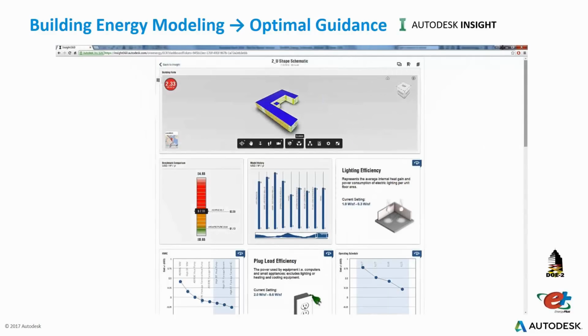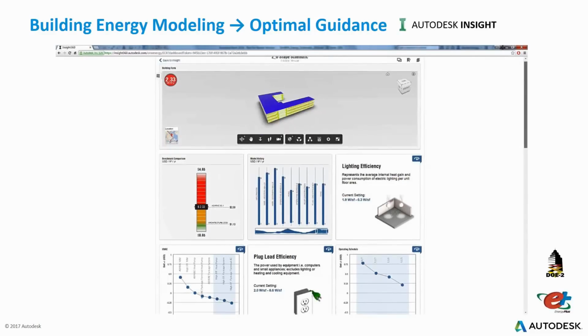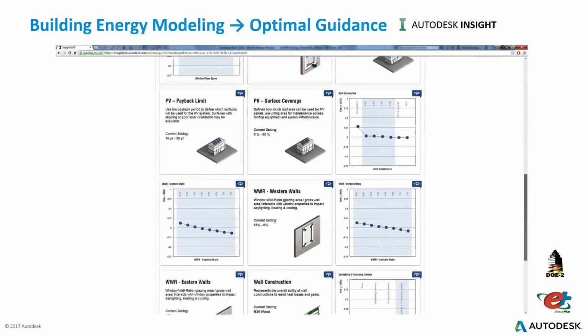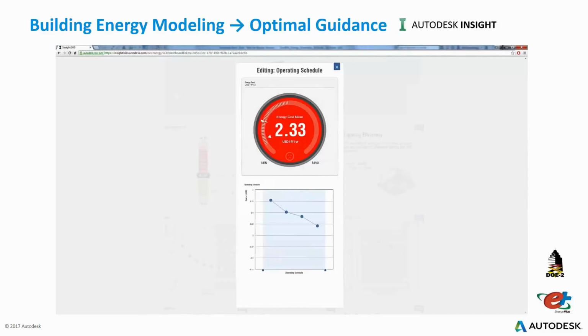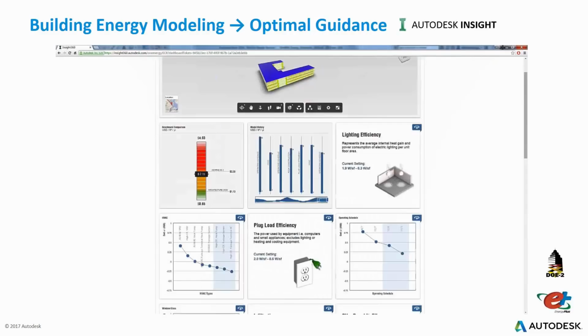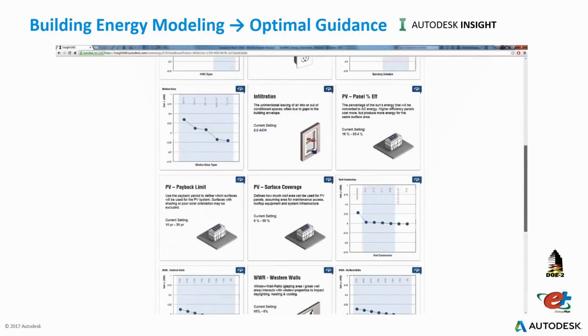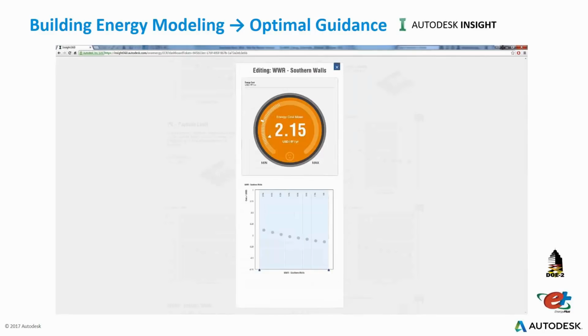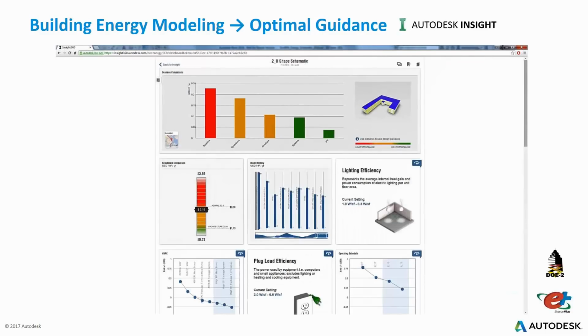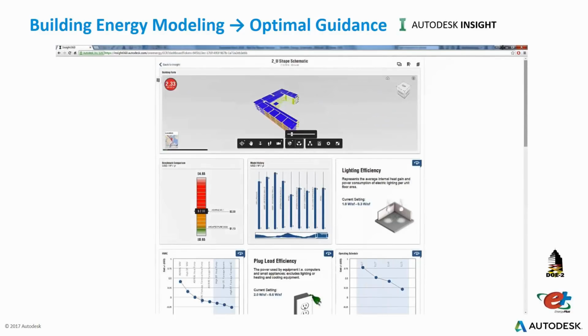It allows us to work with as much or as little specificity as we want. Certain parameters we just don't know, like maybe it's a speculative office and we don't know the operating schedule. In that case, it's better to encompass the uncertainty and optimize the building for a range of potential operating schedules, rather than optimizing for a single artificial, and by definition wrong, point of performance.